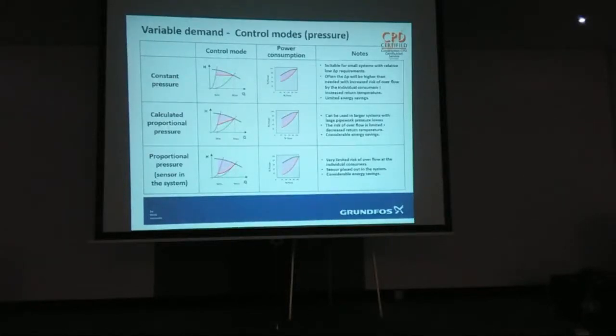That sensor then goes back to the pump, not via the building BMS, back to the pump, and the pump will maintain constant pressure at the point of measurement. The curve it produces will be up that line there. It could be a straight line, but more often it's slightly bowed. And that is ideal where you've got lots of consumers coming off before the measurement. Because if you know the index circuit's getting it, everybody else has got to get it. Simple. Works every time.